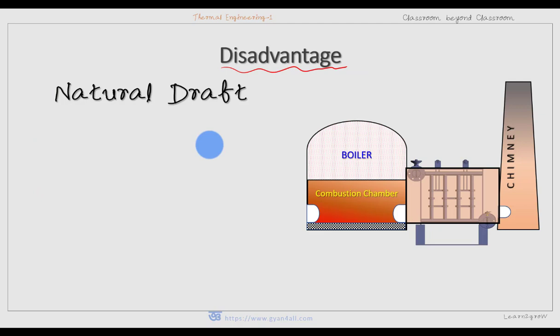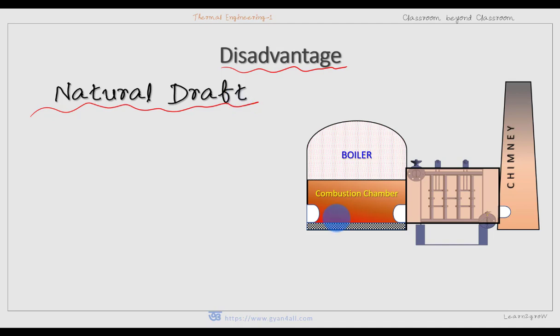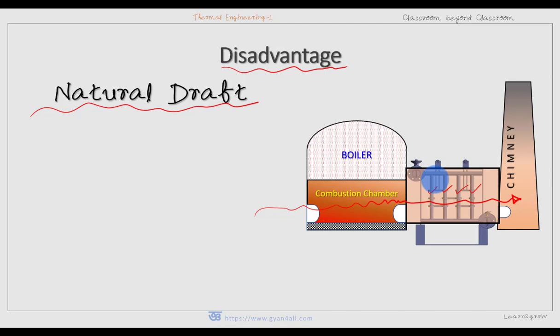One disadvantage of having an economizer is related to natural draught: it reduces natural draught because it obstructs the passage of flue gases. The hot gases from the combustion chamber must pass through the economizer pipes on the way to the chimney, and these pipes obstruct the flow. In a natural draught system, the pressure difference is already very small, and part of that pressure is lost due to this obstruction.